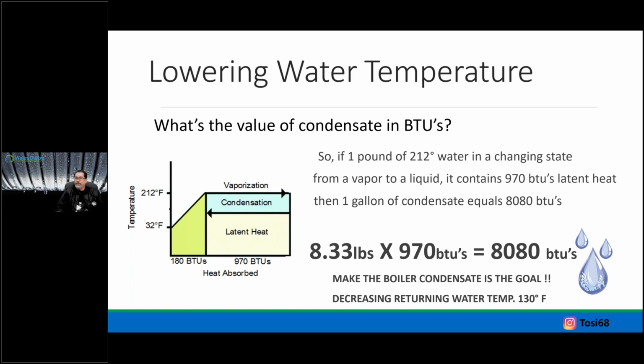No. Maybe not, because the building envelope loses more on the coldest day. It loses less on a 35-degree day versus a 10-degree day. So now I only need to deliver 100-degree water, 108-degree water, 110-degree water. So imagine now what we're achieving on that product of combustion, and condensing, collapsing, and just going in the right direction now. All right.